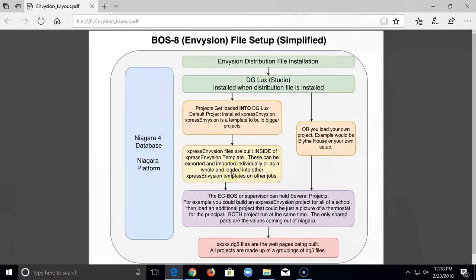So you're either building inside of xpressEnvysion, or loading a project that's not using xpressEnvysion — one of those two. Now here's where it gets more complex: on an EC-BOS you only have one database file. But inside DG Lux Studio you can run multiple projects — you can run a hundred projects. So you can have an xpressEnvysion project, your own project, five other projects, one built just for the CEO, one for the energy manager — all on one EC-BOS. That was the part that gave me the most trouble; I was thinking it only runs one project.